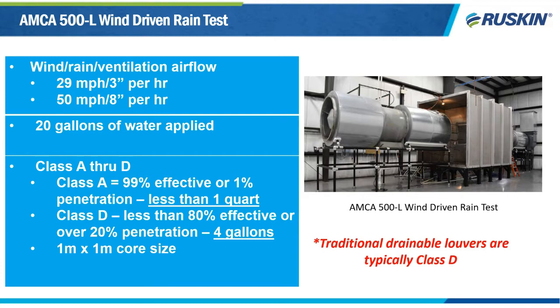A class A rating means that the louver allowed no more than 1% of the water through it that would go through a 1 meter by 1 meter clear opening without the louver, or what we call the core plate. Another way to describe class A is 99% or better efficiency. On the other end of the rating scale, a class D louver allows more than 20% of the water through it, or another way of saying it is less than 80% efficient.